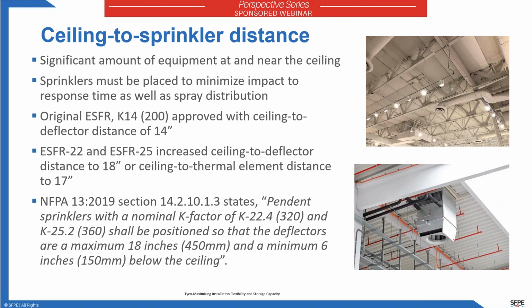As I mentioned, the sprinklers respond to heat. And if the heat doesn't get to a sprinkler, it's not going to operate the sprinkler. And when the sprinkler does operate, it's important that the spray distribution not be negatively impacted by any obstruction that's close to the sprinkler, so the water ends up where it's supposed to go, down below the sprinklers.